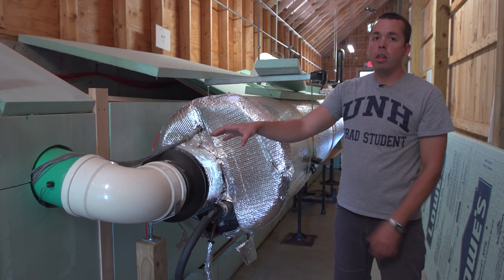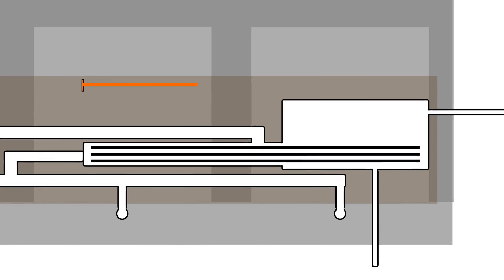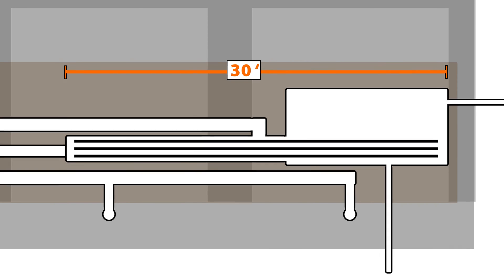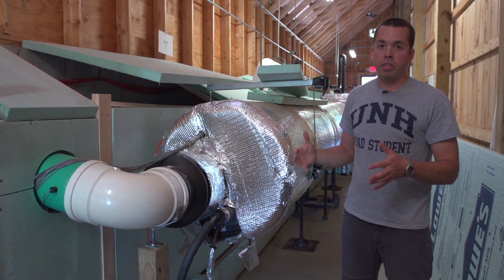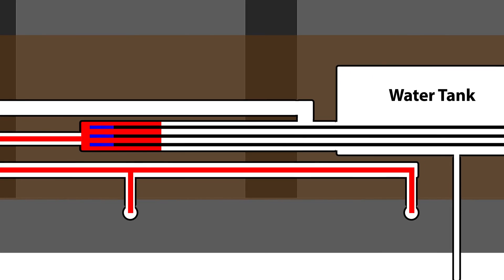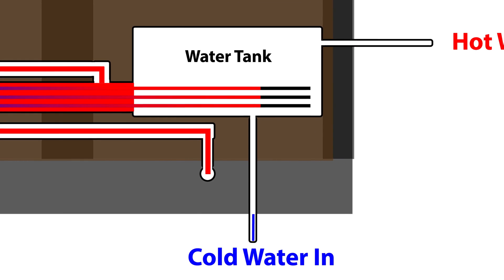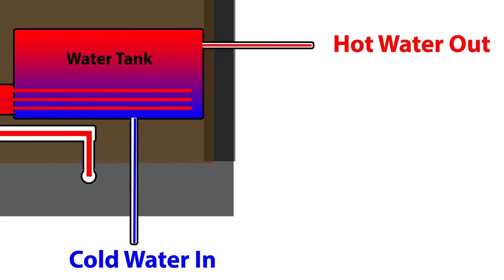All the heated vapor from all the composting bays goes into this giant heat exchanger right here. It's 30 feet long, and 20 feet of it are contained within this vapor chamber with a stainless steel pipe in there. When we warm up this 20-foot section, it warms up the 10-foot section within the water tank, and then we can use that 120-degree water for our basic on-farm needs.